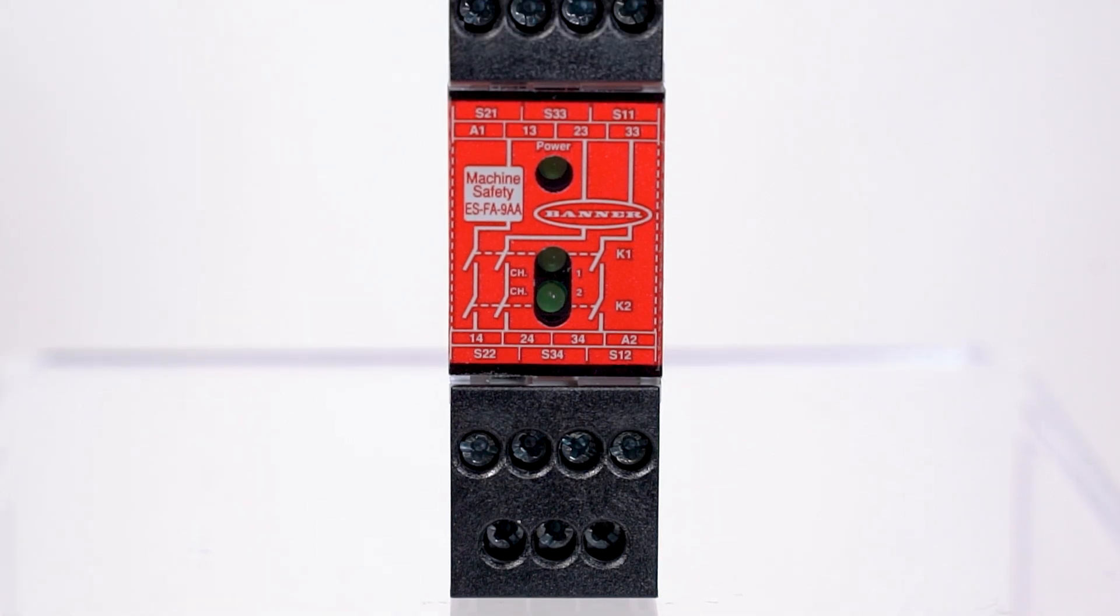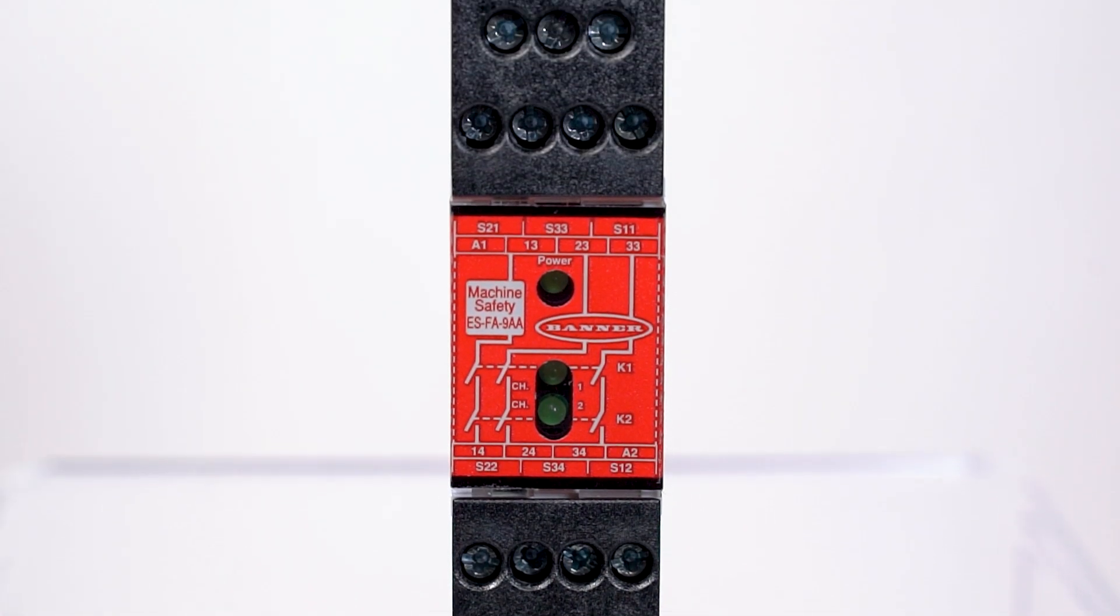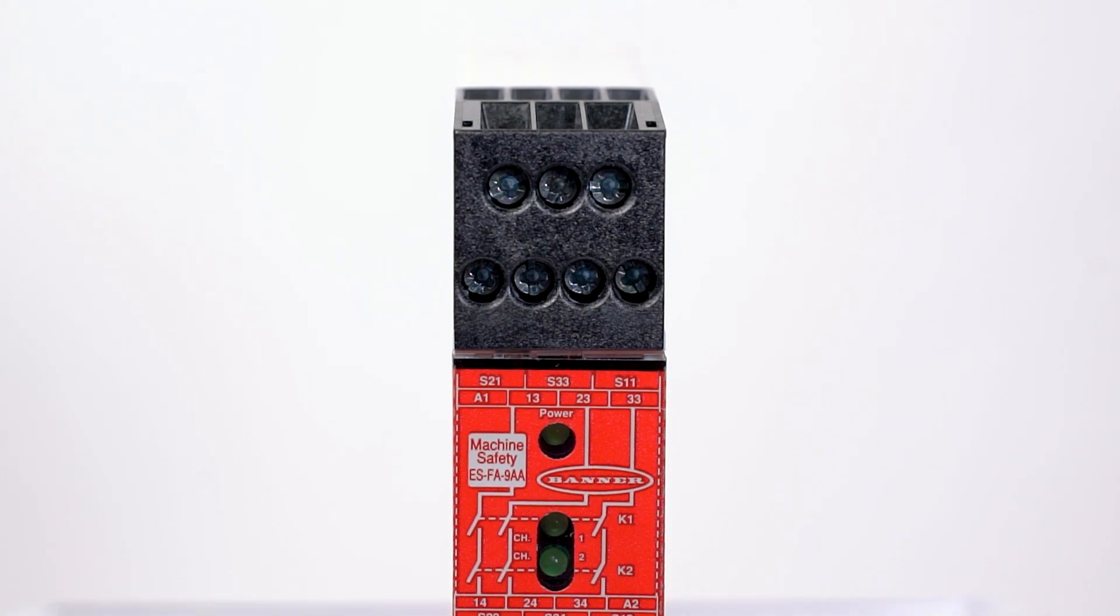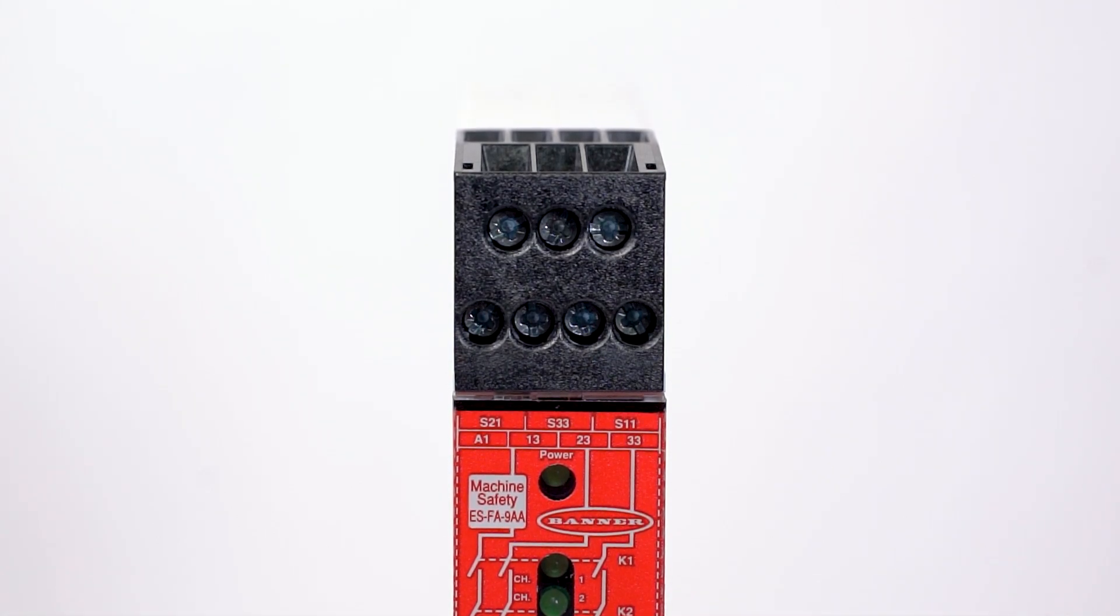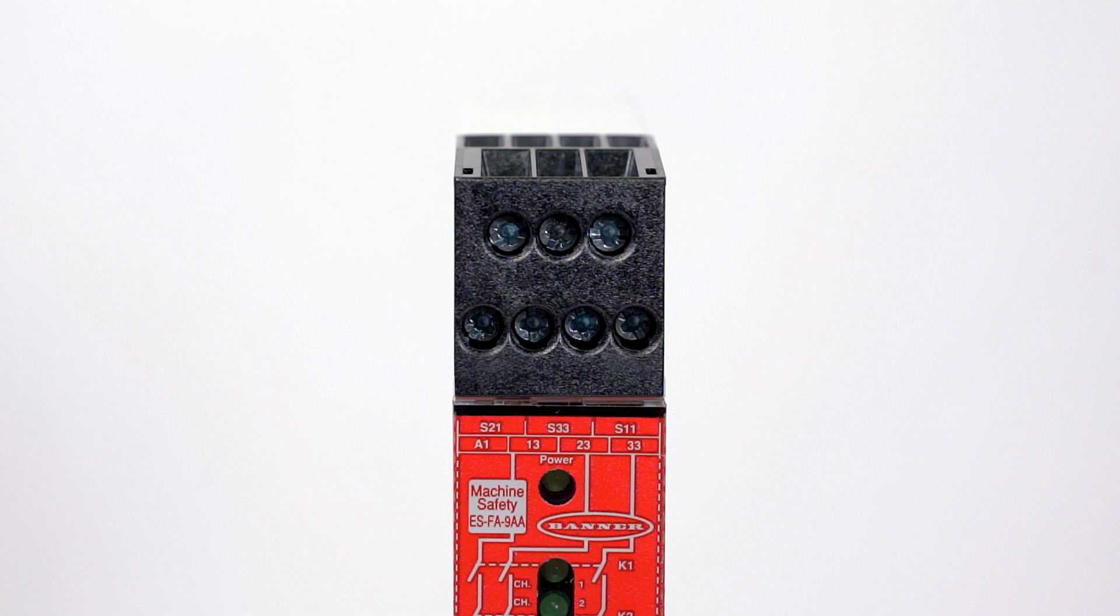It's important to note that the ES-FA-9AA and-11AA modules are compatible with dry contact e-stops only, solid-state e-stops are not compatible.